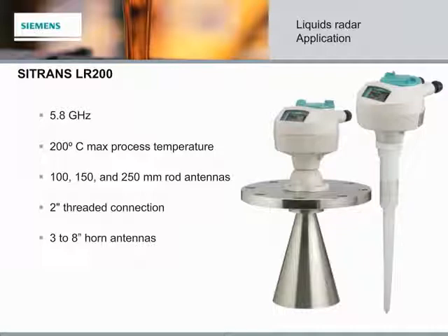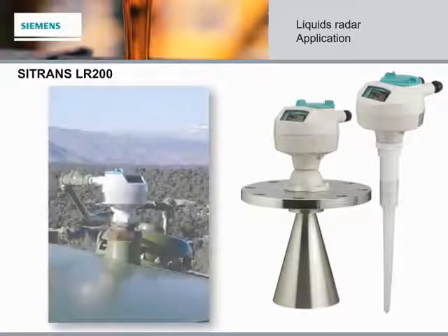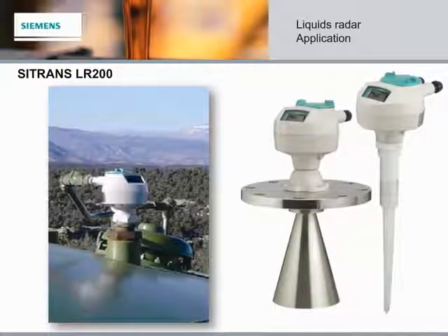Next up is the SITRANS LR200, a two-wire, 6 GHz pulse radar level transmitter for continuous monitoring of liquids and slurries in process vessels, including both high temperature and pressure, and up to a range of 20 meters. Key applications for the LR200 include liquid process vessels with agitators and/or turbulence, vaporous liquids, high temperatures, anaerobic digesters, asphalt, and other sticky products that can build up on the antennae.